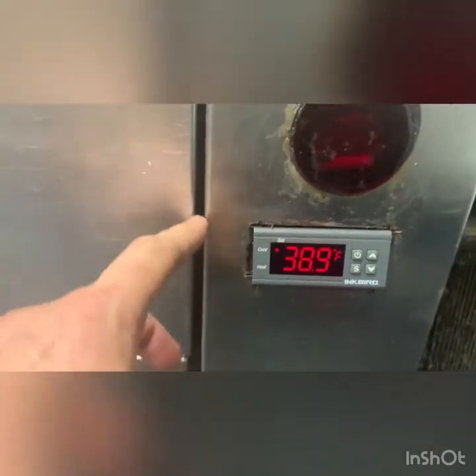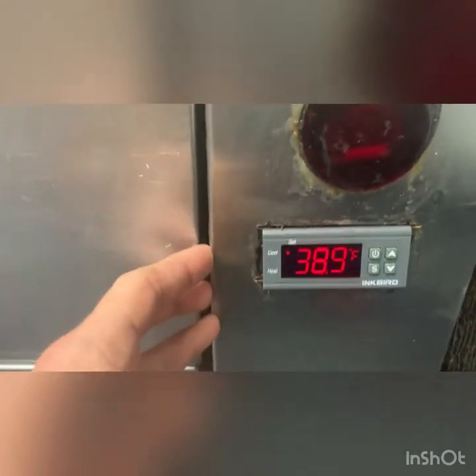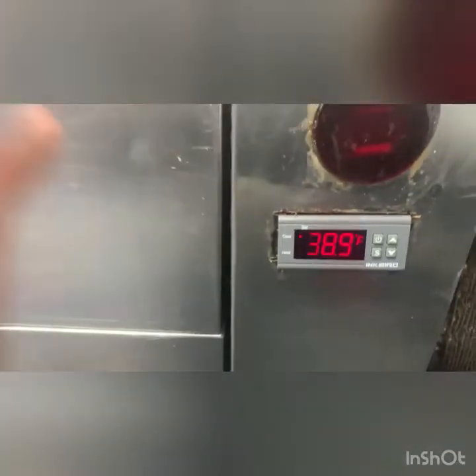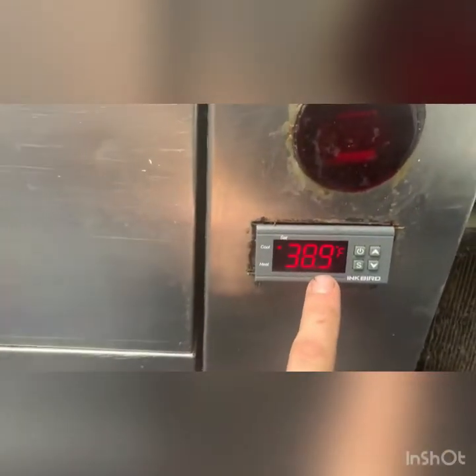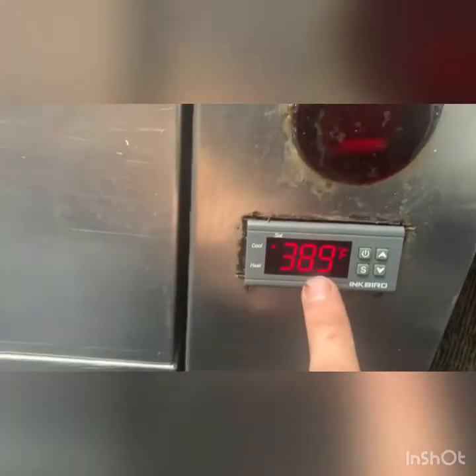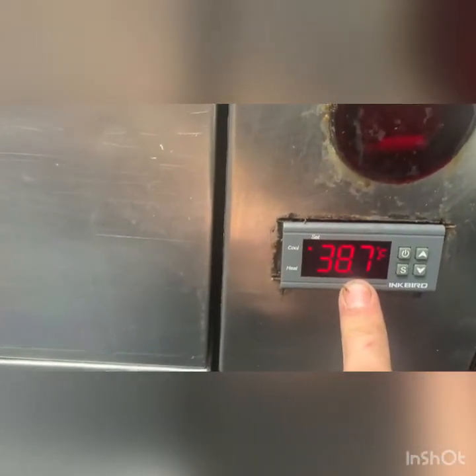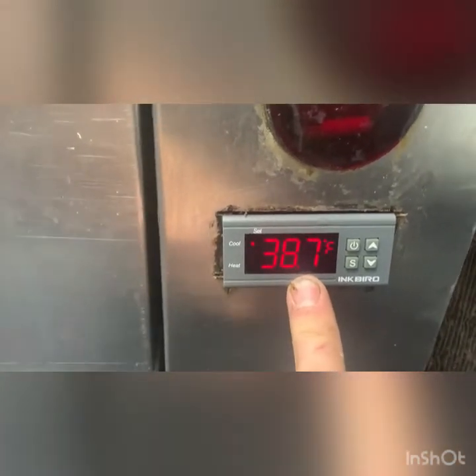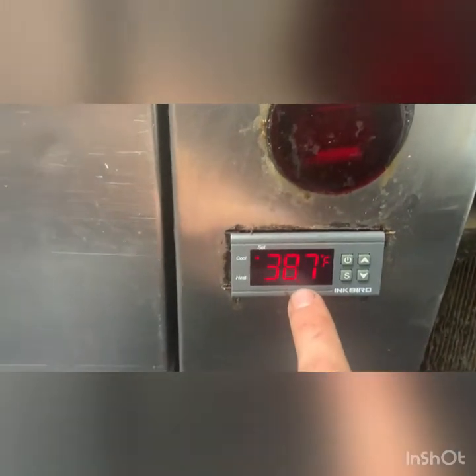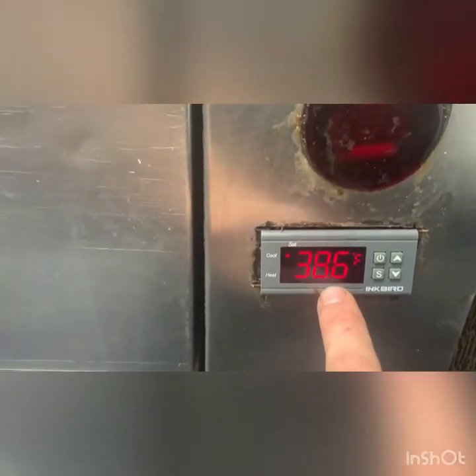So coolers generally don't need a defrost. They defrost when they satisfy, which is why if they leave the door open, it's going to just let hot air in. It never satisfies. The coil never gets to be 20 degrees, and it just runs itself to a solid block of ice and bad things. So we are cooling. We're just going to wait, make sure the box cools down to temp and satisfies, and then we're out.